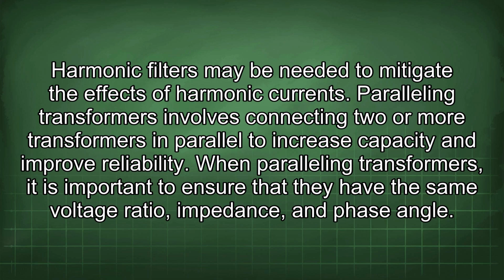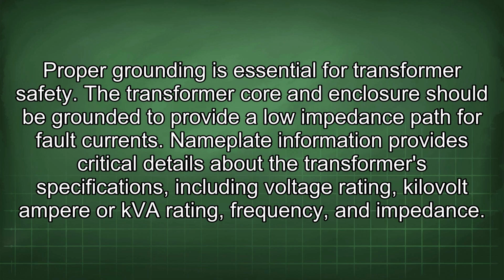Paralleling transformers involves connecting two or more transformers in parallel to increase capacity and improve reliability. When paralleling transformers, it is important to ensure that they have the same voltage ratio, impedance, and phase angle. Proper grounding is essential for transformer safety. Transformer core and enclosure should be grounded to provide a low impedance path for fault currents.